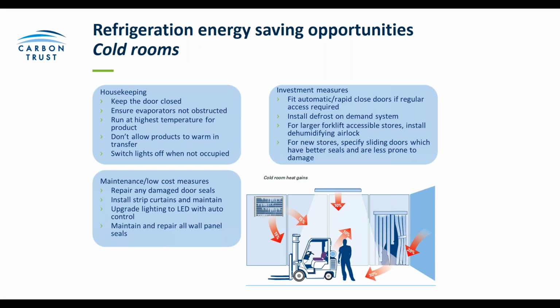In terms of maintenance and low-cost measures that you could implement, repairing damaged door seals to make sure there's no transfer of air between the rooms, that is really important. Automatic and rapid closing doors are probably the best practice for this type of space. Strip curtains are really useful if they're well maintained at keeping the warm air in and the moisture out. And make sure that the outside of the cold store is sealed airtight with no gaps in any panels or joints, and the insulation is covered throughout.